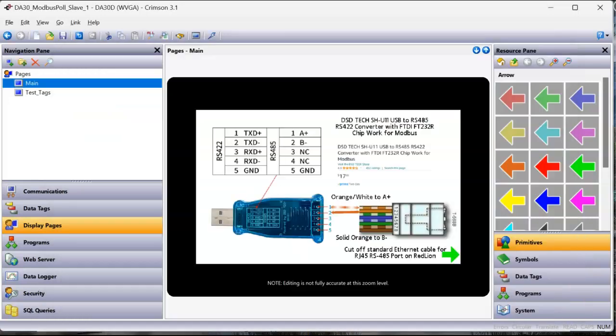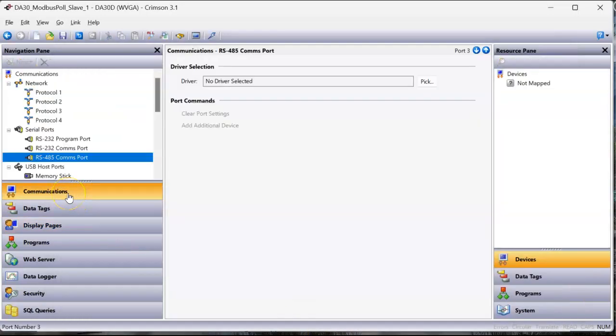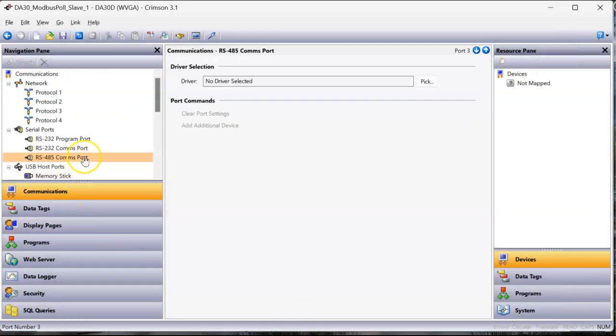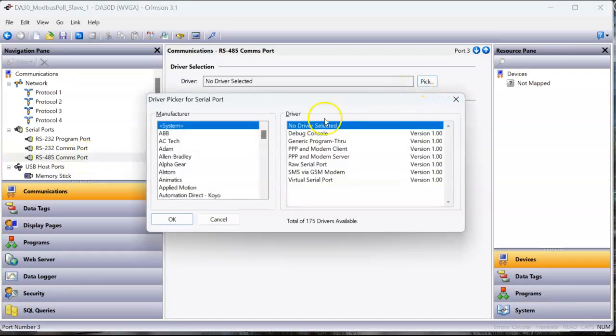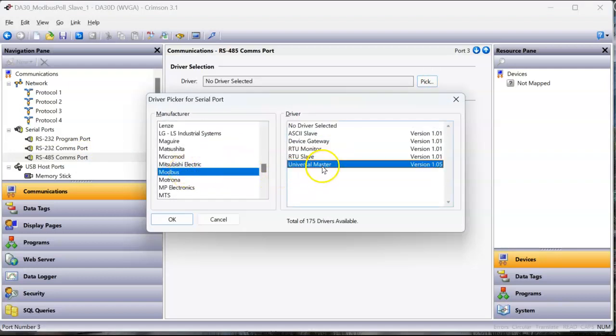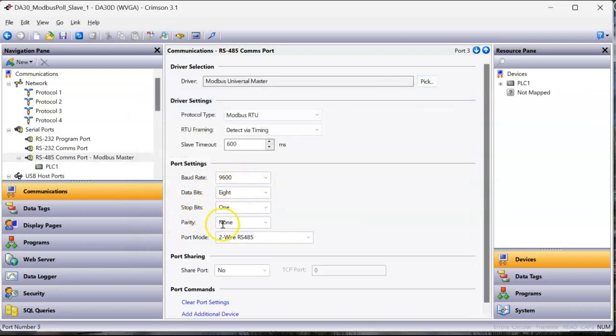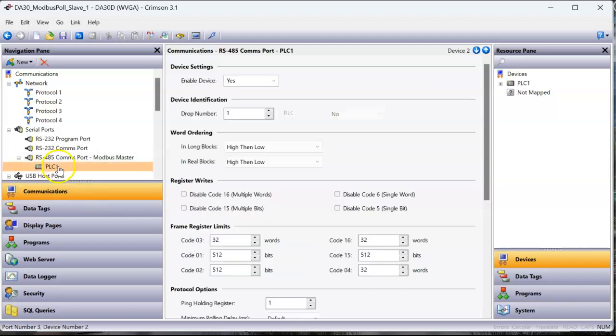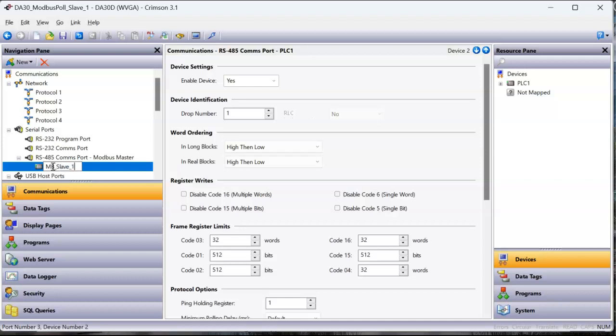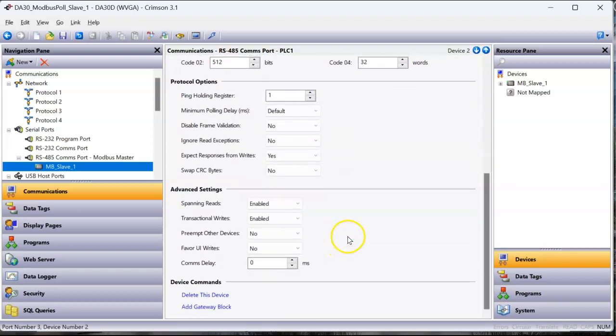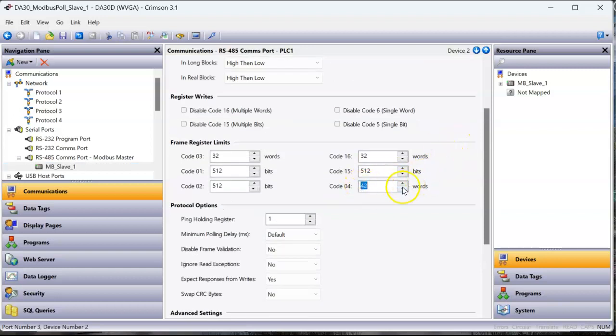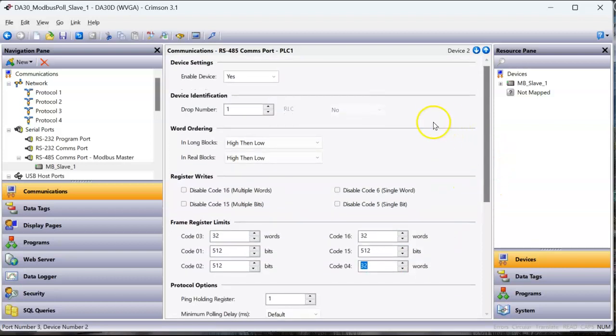Let me go back to Red Lion here, and I'll go over here to communications. I'm going to click on the RS-485 port. Hit pick driver. I'm going to go down to Modbus for my driver here, and I'll pick universal master. 9600, 8, 1 and none is the default setting here. I leave it at the same. Let's call this MB_slave_1. I picked that name because here's the slave number. I'm going to leave everything else in here as default. So I'm not doing any changes. All of this is the default setting. So it's all the standard settings.